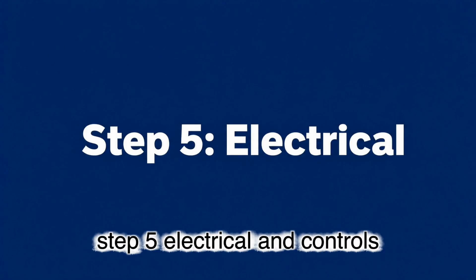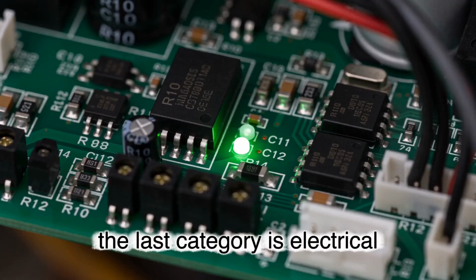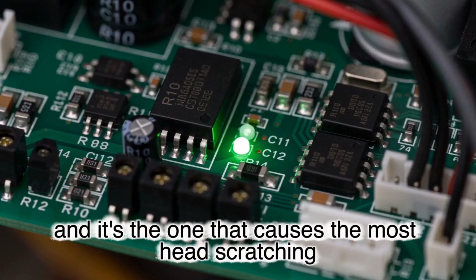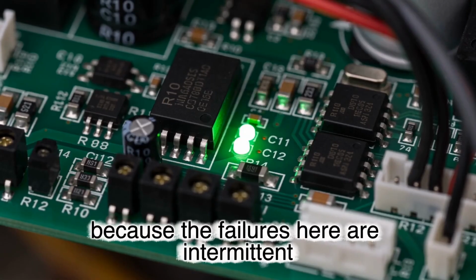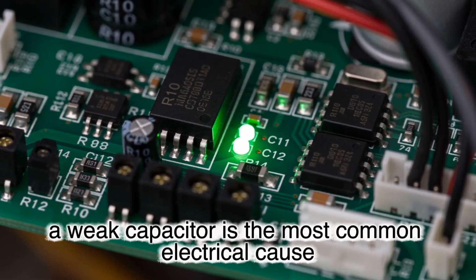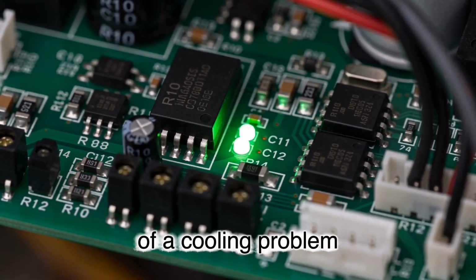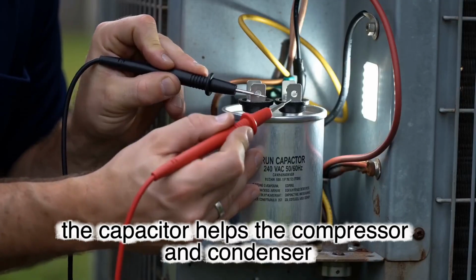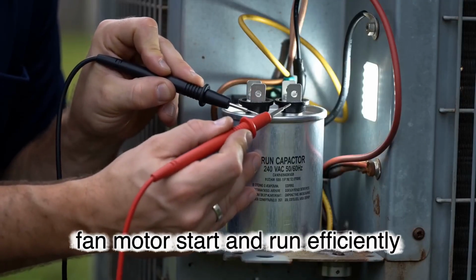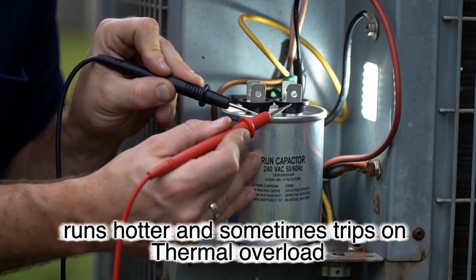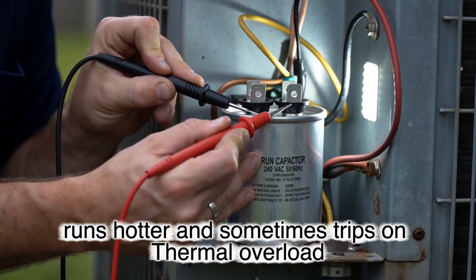Step 5, electrical and controls. The last category is electrical, and it's the one that causes the most head scratching because the failures here are intermittent. A weak capacitor is the most common electrical cause of a cooling problem. The capacitor helps the compressor and condenser fan motor start and run efficiently. When it degrades, the motor works harder, runs hotter, and sometimes trips on thermal overload.